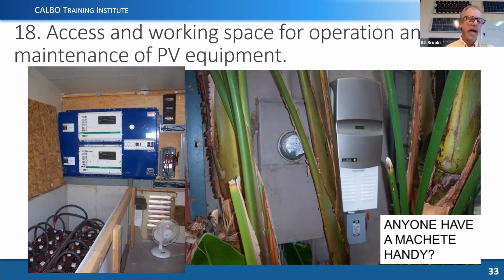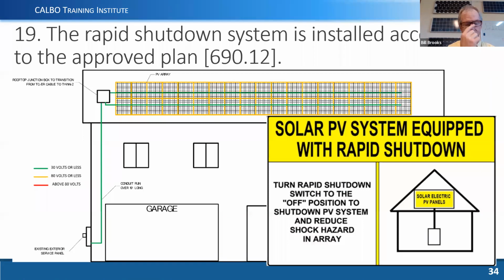But anyway, having proper access to equipment, sometimes, especially with batteries, we do have to think it out, and it's not simple. It's not easy. We have to really put some thought into that when we're laying out equipment on a system. And that's one of the reasons why, if you can have that in your plans and get that approved and talk to the local jurisdiction, then those issues can be resolved ahead of time and you don't have to deal with that in the field.